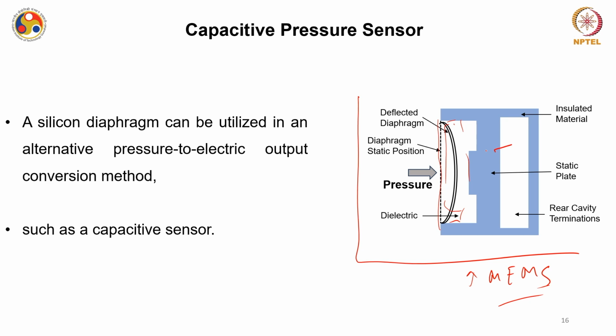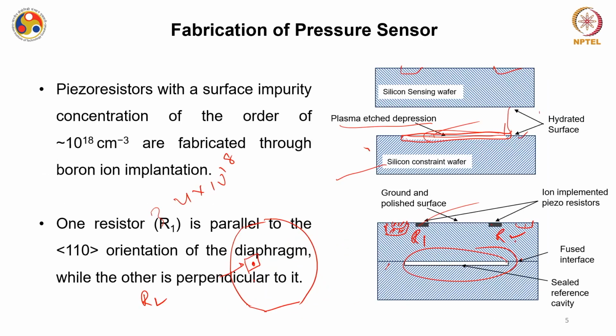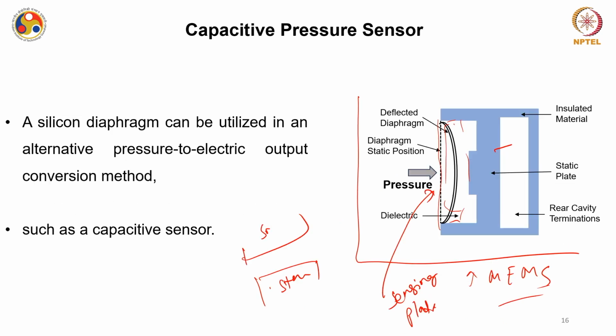This plate is known as the static plate. If I call this diaphragm a plate for now, this is my sensing plate, and the other one is the static plate — similar to before, where we had a sensing wafer and a static or constraint wafer. So you have this sensing plate, or diaphragm, where you apply pressure, and the diaphragm deflects from its original position to a new point.